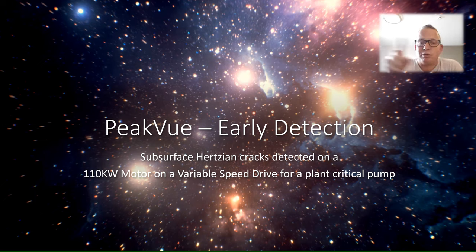So as the rolling element goes round, we've got a slight dent in the load zone, we get plastic deformation where the grease also goes solid, stops the metal hitting the metal, but the ball bearing and the metal sort of flex a little bit. So you get subsurface fatigue.